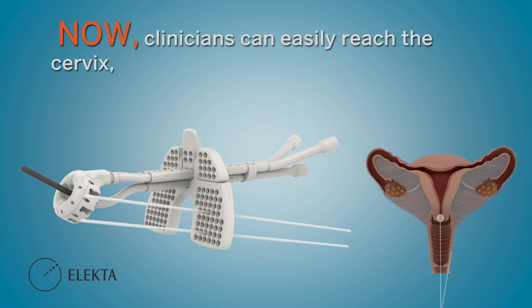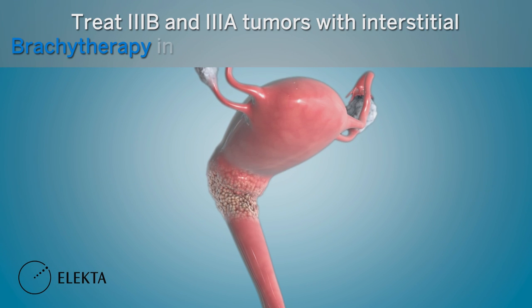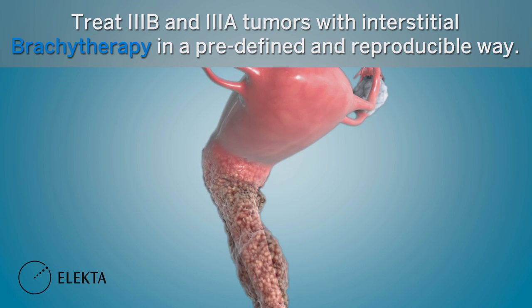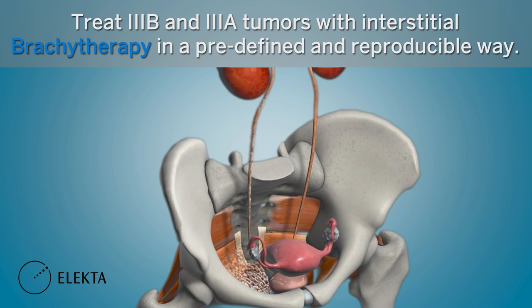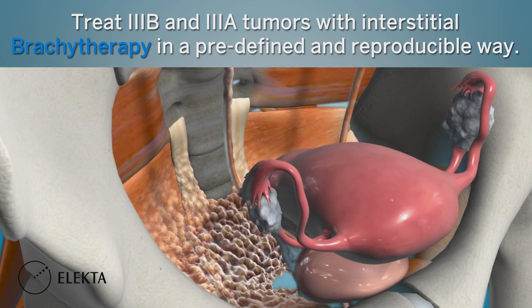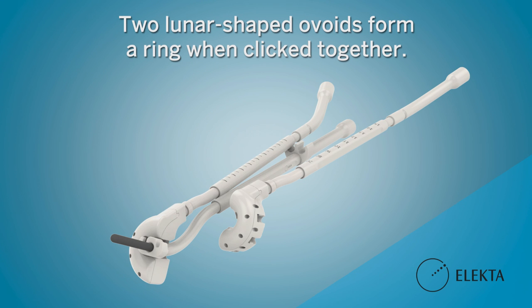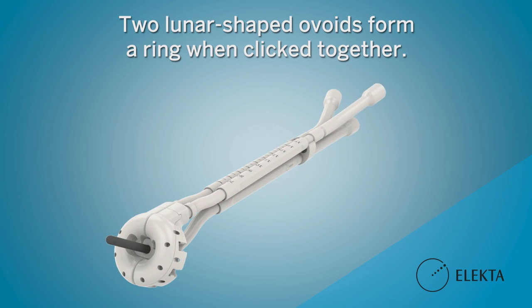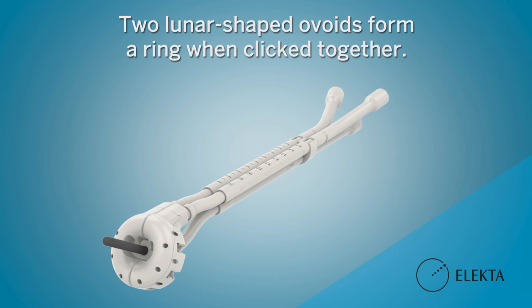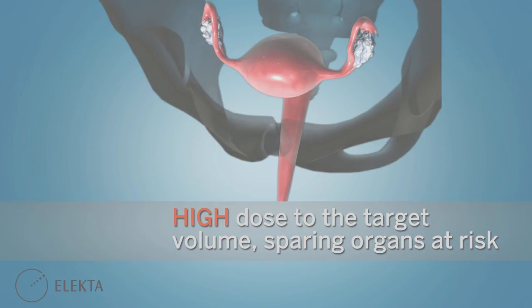Now with Venezia, clinicians can easily reach the cervix, parametrium, and vaginal extensions. Venezia enables physicians to treat 3b and 3a tumours with interstitial brachytherapy in a predefined and reproducible way. The two lunar-shaped ovoids form a ring when clicked together, allowing you to benefit from the advantages of a tandem and ovoid applicator in combination with the dose distribution of a ring — delivering high dose to the target volume while sparing organs at risk.